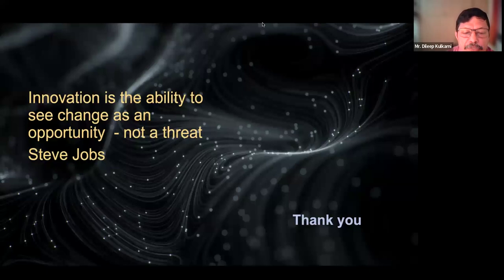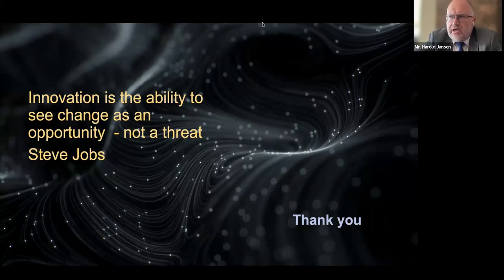Then you have a question from Mr. Anirban Datta. How is advanced NDT used in a newly built plant before commissioning is done, or maybe during the commissioning stage? Within the power generation industry, we had two new build projects, I think starting roughly 2010. From the onset, normal conventional NDT was done. And then as a result of the construction process, slowly but surely, for example, phased array testing of the welds in the boilers was conducted. And there were a few issues that were identified, and consequently they were also fixed.